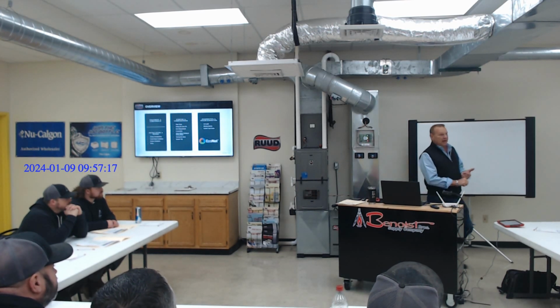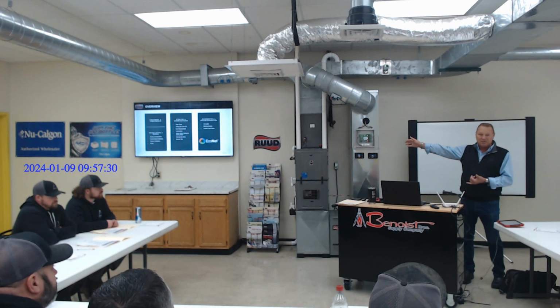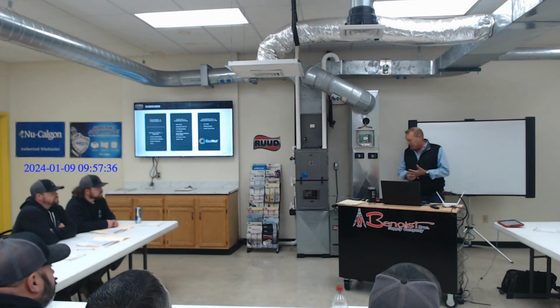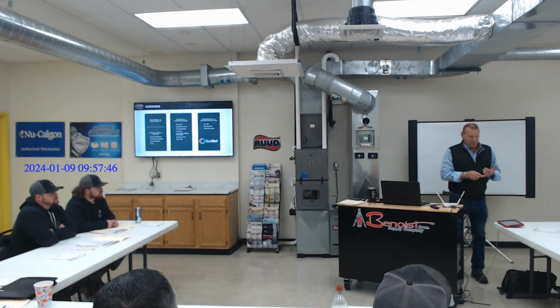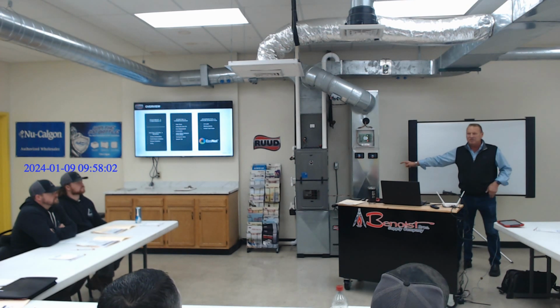These motors measure static pressure based off the torque on the shafts. The torque on the shafts is communicating to the module, which is breaking it back down into CFM and static pressure on these thermostats. That's how they're getting CFM numbers, based off the torque through the communication process, okay? There's a key on here, and it's the RPMs of the motor. On all of our ECONETs, when you go to your air handler or furnace, you can see CFM, static pressure, and RPMs. If you don't walk out of here understanding anything else, the key RPM number is 1250. If you're running over 1250 on these motors, I guarantee you you're running over an inch of static.